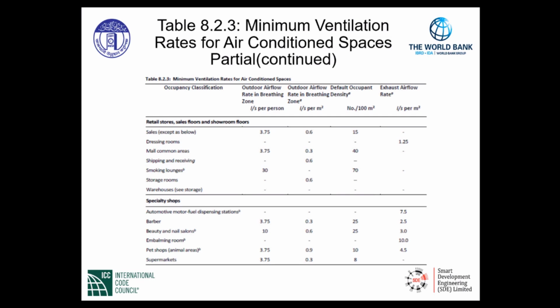As you can see, there are four values in the table. The first value is 10 liters per second per person in the first column. That's our people airflow rate. The next column is 0.6 liters per second per square meter. That's our area flow rate. And we can calculate the people or the population in the zone by simply looking over the third column and running that ratio, if you will, in a calculation at 25 occupants per 100 square meters.